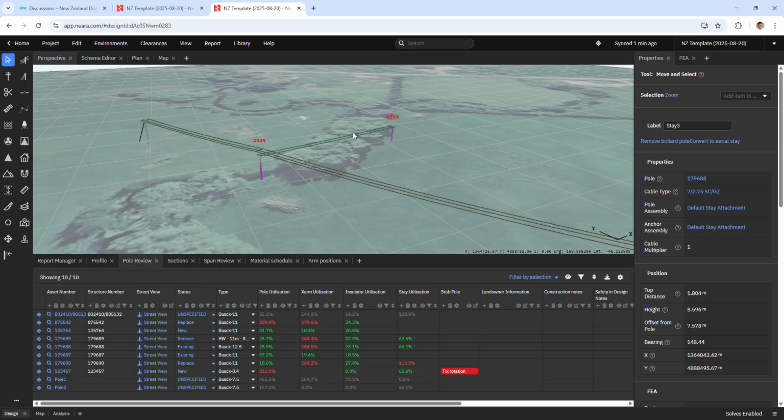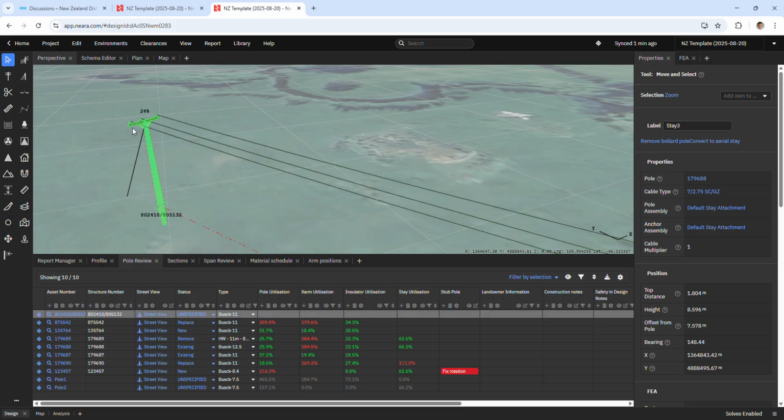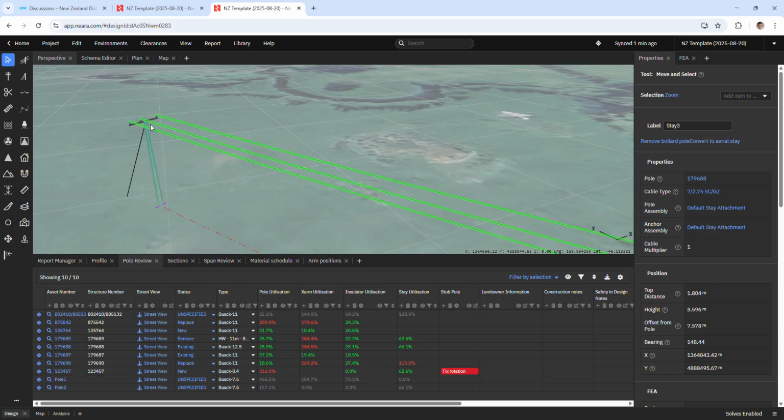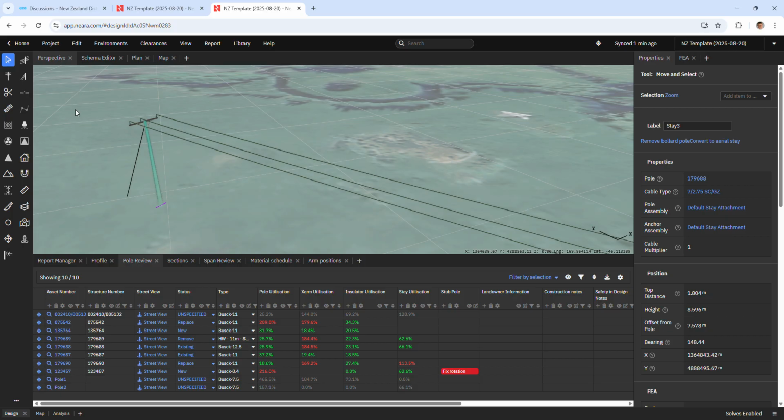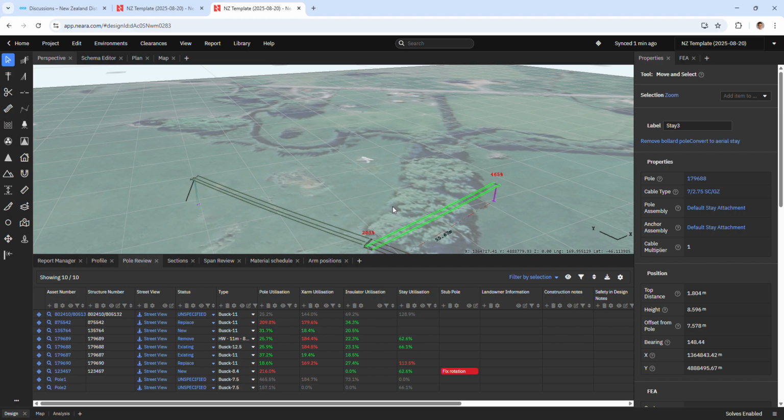And we do this in our modeling because this pole here's got a takeoff on it, and so when we model this pole, we want to model it with those takeoff loads, and it's got a span going in this direction as well, so we go one span in this direction so that we've got that loading on there. But the thing is that this pole here, if we look at it, it's an intermediate pole. It continues in that direction forever, or however far it goes. And so it's likely to be overloaded, or the crossarm's probably overloaded, and same deal for this one.